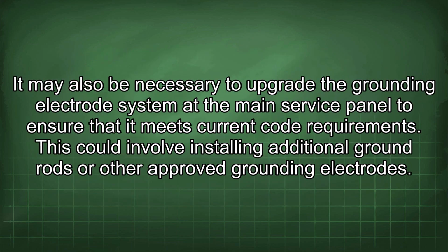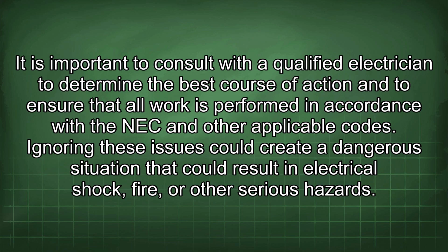It may also be necessary to upgrade the grounding electrode system at the main service panel to ensure that it meets current code requirements. This could involve installing additional ground rods or other approved grounding electrodes. It is important to consult with a qualified electrician to determine the best course of action and to ensure that all work is performed in accordance with the NEC and other applicable codes. Ignoring these issues could create a dangerous situation that could result in electrical shock, fire, or other serious hazards.